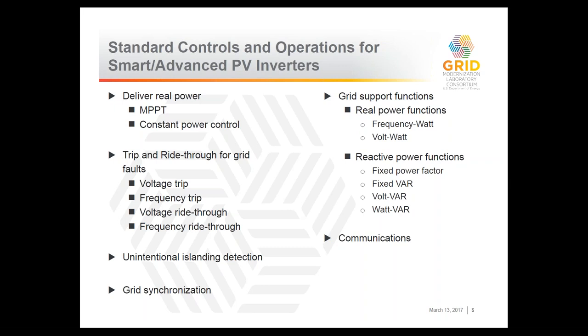For example, real power functions such as frequency-watt and volt-watt. And again, I am not going to go into the details of every function for the sake of time, but this is a snapshot that is coming from new interconnection standards such as the revised IEEE 1547, which is currently under development. Reactive power functions similarly include fixed power factor, fixed reactive power, volt-var, watt-var, and some other versions of those. And another important thing coming into all those new inverters is some form of communication. Most of them have a proprietary communication, and some of them also have standard communications to talk to those inverters.